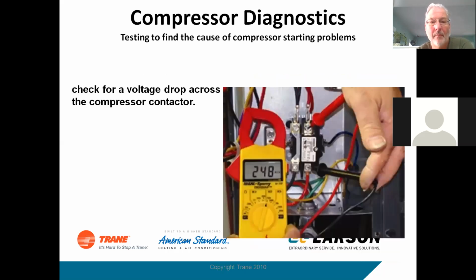Check for voltage drop across the contactor. Put your meter across there. It should be, you know, it should be 0 voltage drop across there. So if you're getting a voltage drop across the contactor, that means the contacts are burned or pitted. Things are just not, you know, the way they should be. Contactors are pretty cheap. So if you suspect the contactor, back in the old days, we always carried contact point files and we would clean the contacts, but you know, put a new contactor in if you suspect that there's something going on with it. It's just cheap insurance for the life of the compressor.